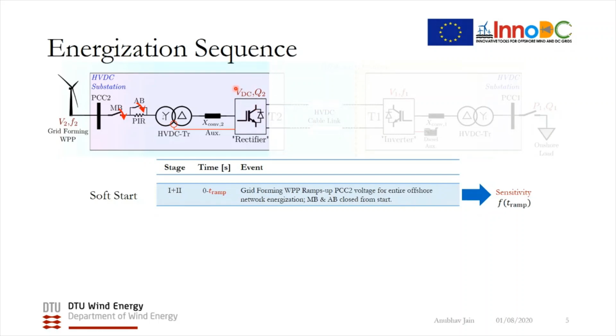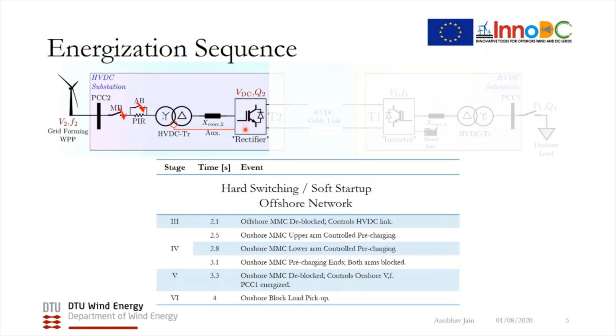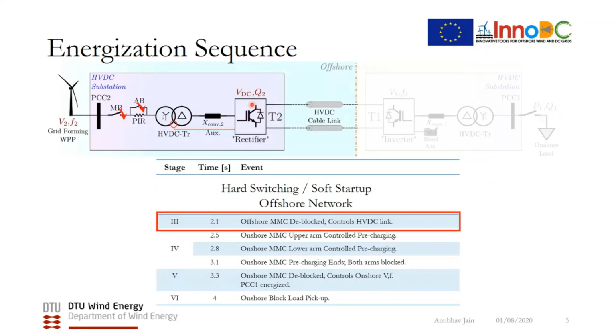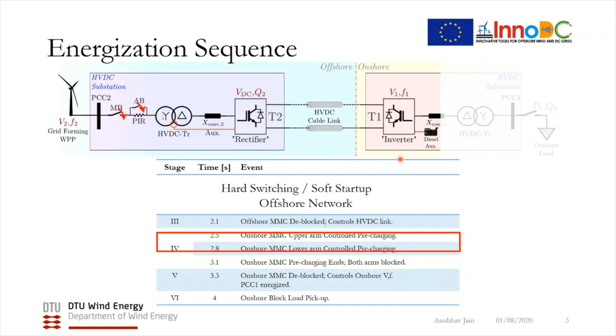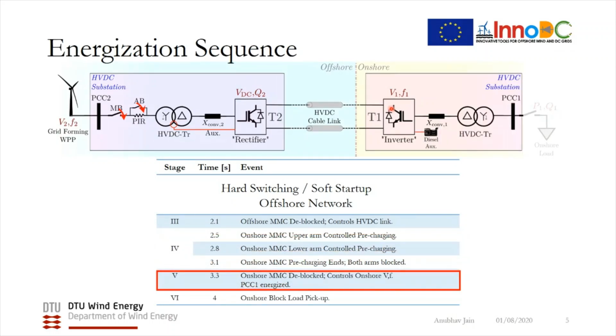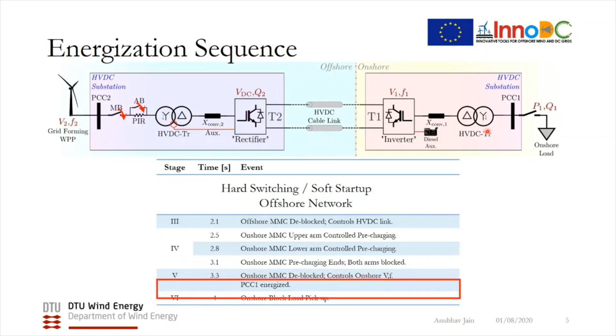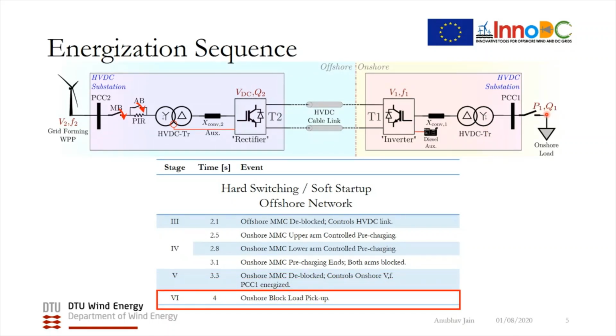Once the offshore network is energized, then the offshore MMC can be deblocked to control the DC link voltage of the HVDC link, which is then used to precharge the onshore MMC, as I showed with this controlled precharging sequence. After that, once the cells are fully charged to their rated values, we can deblock so that it starts controlling the onshore voltage and frequency. Finally, the block load is connected to demonstrate the energization capabilities of this HVDC connected offshore wind power plant.